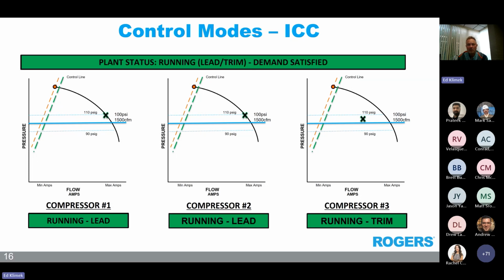So what this animation doesn't show, though, is a high system pressure situation. If it did have a high system pressure situation, the third compressor, being the trim machine, would eventually blow off, and then it would shut that unit down.